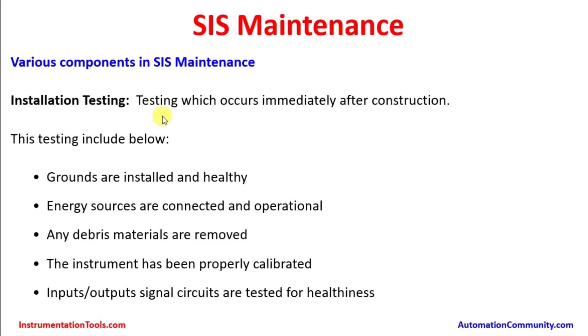We will now go over the critical items important for SIS maintenance. The first is installation testing — testing which occurs immediately after construction. This includes ensuring grounds are installed and healthy. All instruments installed, whether at the plant site or in the control room enclosure, must be properly grounded so that any fault on the instrument or prior line can be grounded and accidents due to wrong grounding can be avoided.